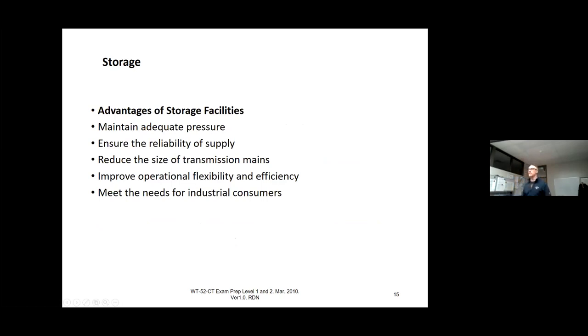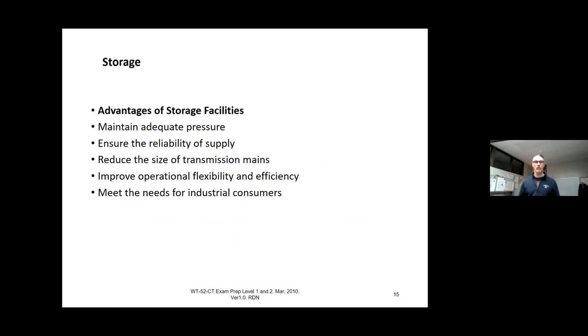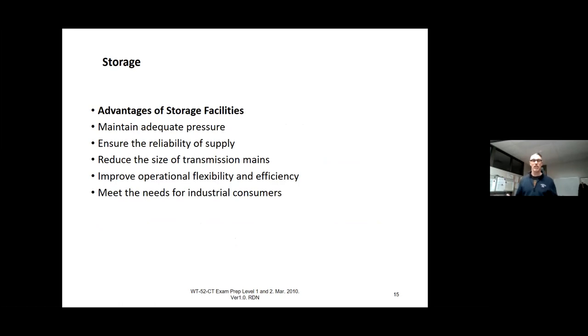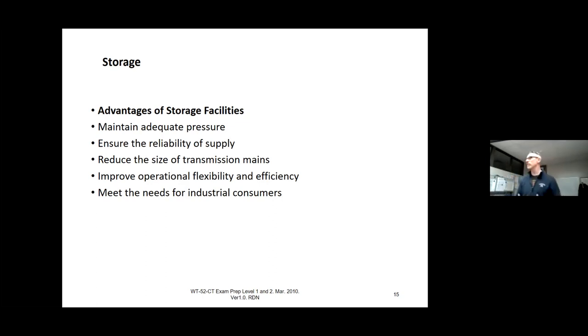One of the advantages of storage is that it maintains adequate pressure. It's really important not to fluctuate pressure in your system — if you do, your pipes or your customers' taps and piping will be damaged. If you have more storage you can make your piping smaller, because I don't have to run huge pipes all the time. It also improves operational flexibility — I can turn things off to do maintenance, turn down the flow, turn up the flow, and change things in my process.